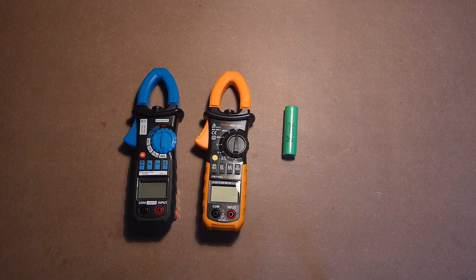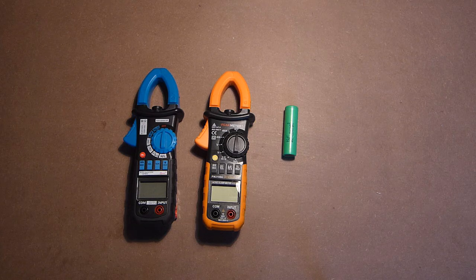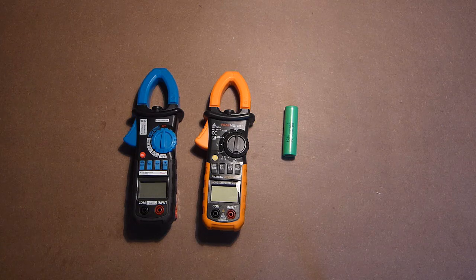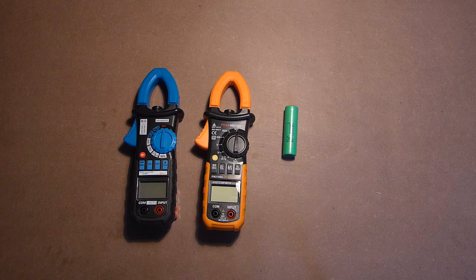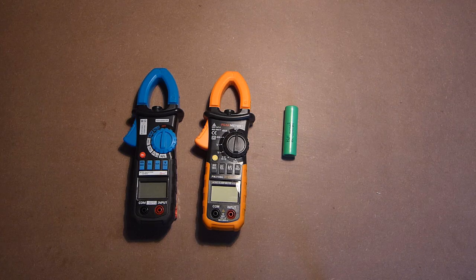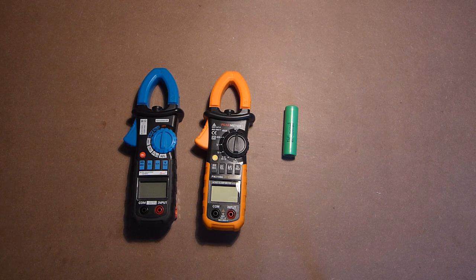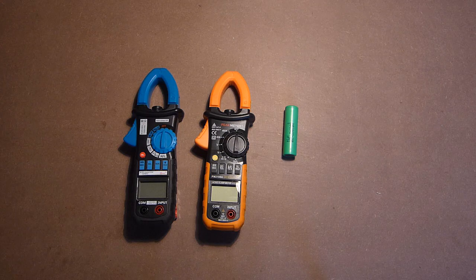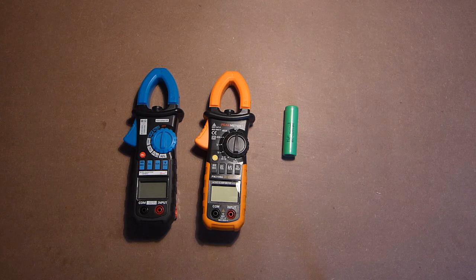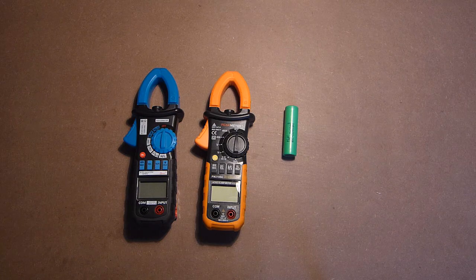I can say that the devices have absolutely the same accuracy, but anyway the clamp meter itself is not a very precise device. However, in all conducted tests these two devices have shown almost the same results. In my opinion, there is no sense to pay for B-Sight when a Peak Meter has almost the same accuracy but is cheaper at the same time.